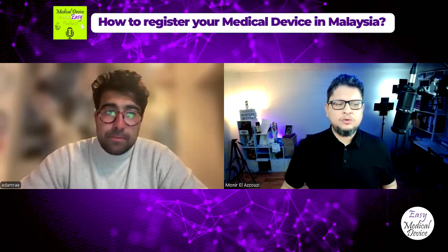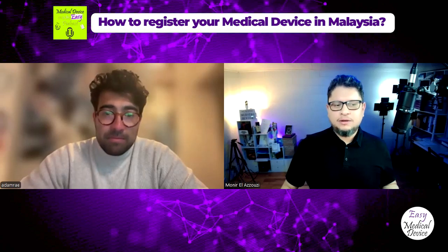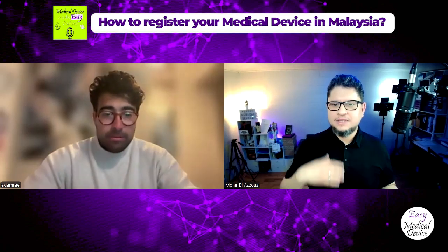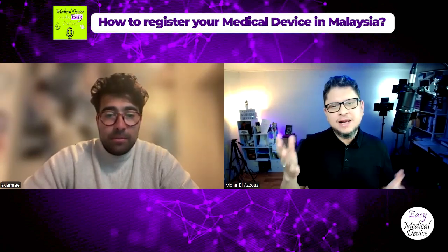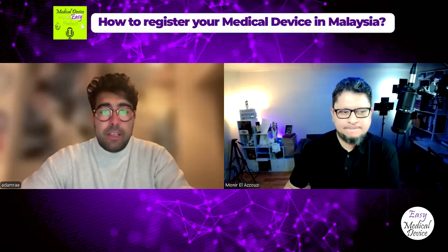Again, who is doing this verification? Is it the conformity assessment body or is it the authority? It is a conformity assessment body. So if you have, for example, a product located in Europe, you have your notified body in Europe. So it's not sufficient. You still have to go through a conformity assessment body that will review all what was done in Europe for then assessing. And as you said, it's a light check. It's not like a major burden, if I can say, normally for that.